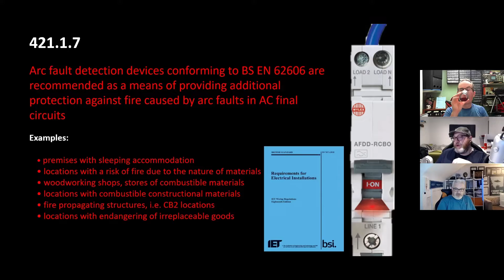What we thought we'd do is remind everybody very briefly that an arc fault detection device is looking for damage or breaks in single conductors. So if there's damage in a flex and there's just one core, that's not going to trip overcurrent protection. It may not trip earth leakage protection. It could be damage within the cable.